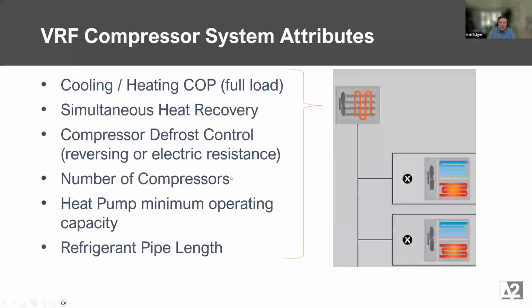But it matters, right? So you can change these properties both in how you pick it and how you model it. You can say I have 3 compressors. The lowest turn down of all of them is 25%. And then you can even define the refrigerant pipe length. The model input tends to not change the results dramatically. It's there. You can play with it and specify it as best you can. We found that it's more the real performance and pipe length is really where it drives the results today. But those are kind of the things we're thinking about, right, with the main compressor.